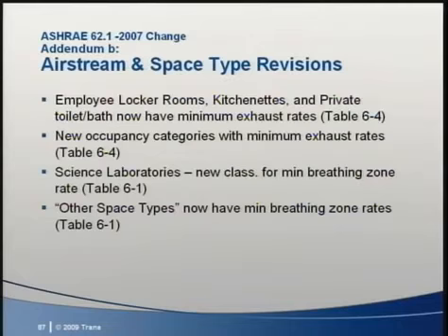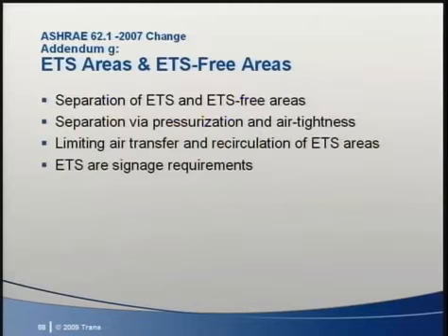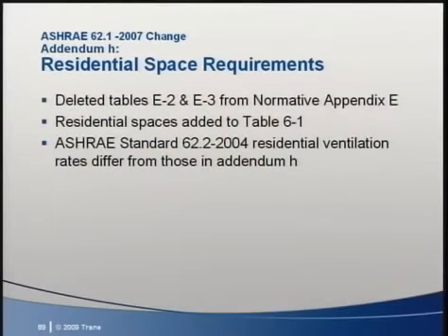Now, Addendum G in brief requires space classification based on expected presence of environmental tobacco smoke, ETS, separation of ETS and ETS-free areas, and cautionary signage for ETS areas. As defined, ETS spaces are those where smoking occurs or those that are not separated from smoking areas. This separation is achieved through a combination of pressurization and air tightness, as well as through limitations on air transfer and recirculation.